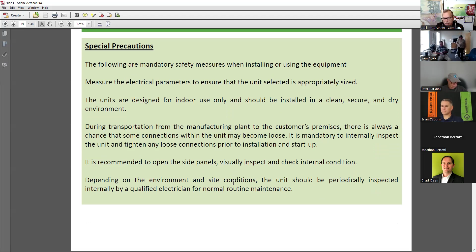But every unit was tested, it's not batch testing that happens. So you need to take the usual precautions that electricians learned. The project manager needs to make sure he is supervising the electrician so they go through the steps, because it takes less than 20 minutes. That can save you 20 weeks of troubleshooting or fixing what you ignored. That 20 minutes is the most expensive 20 minutes for you if there is a problem.